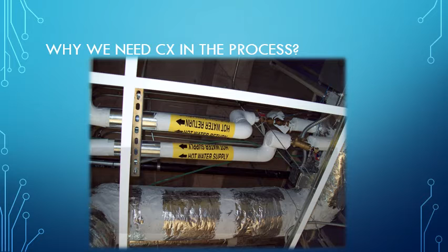Actually, the purpose of commissioning is a collaborative effort. We want to make sure we have identified and addressed the design and construction issues, whether they are okay or not, the operational issues, such as whether our HVAC or AHU system, our air conditioning, operates in good condition. So actually the purpose of commissioning is to be an extra pair of eyes to make sure our design and our assemblies are in good shape.